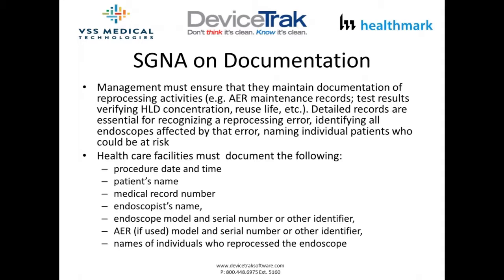SGNA's recent guideline states you should document: the date and time, the patient's name, the medical record number, the physician performing the procedure, the endoscope model and serial number or other facility identifier, the AER model and serial number used, and the name of the individual who performed the reprocessing.